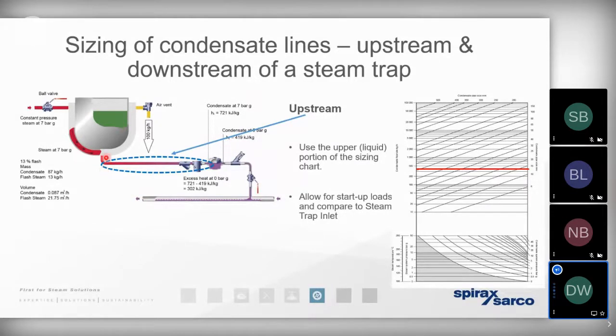In other words, we can size the pipework at this point by simply referring to traditional or typical water pipe sizing charts. And of course, we can download those off the internet, or we can use that very useful little app that we've spoken about. The important thing is allowing for that warming up load. So here we've got an example where we've tripled that 100 kilogram per hour condensate load to allow for the warming up load. We've taken the red line horizontally across, and that's helped us to size the appropriate condensate pipework.